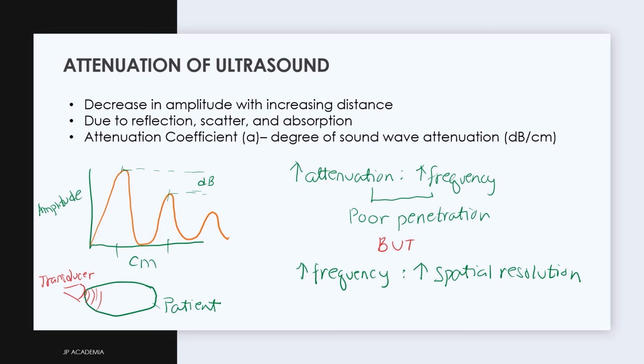We have this attenuation coefficient, which describes the degree to which sound waves attenuate in decibels as they traverse a unit distance in centimeters. This is illustrated in my drawing at the left with the graph of echo amplitude detected by the transducer as a function of distance. The attenuation generally increases with increasing frequency. Thus, higher frequency means poor penetrability. We can only image superficial parts well given a high frequency. But note also that higher ultrasound frequency means higher spatial resolution, or detail of the image. Overall, this is about the compromise between penetrability, or imaging deeper structures, and spatial resolution. And that's it for this lecture.